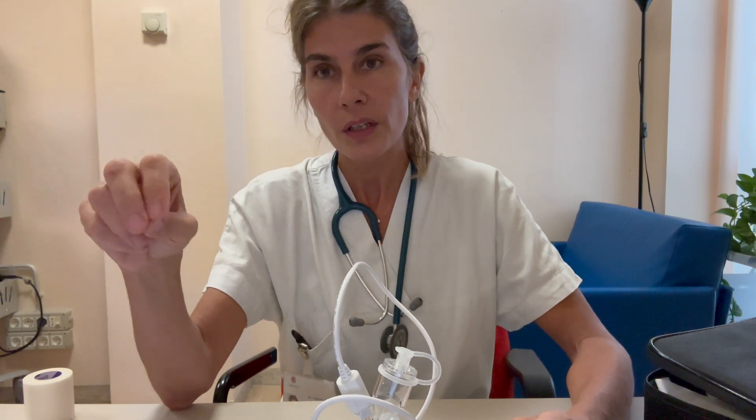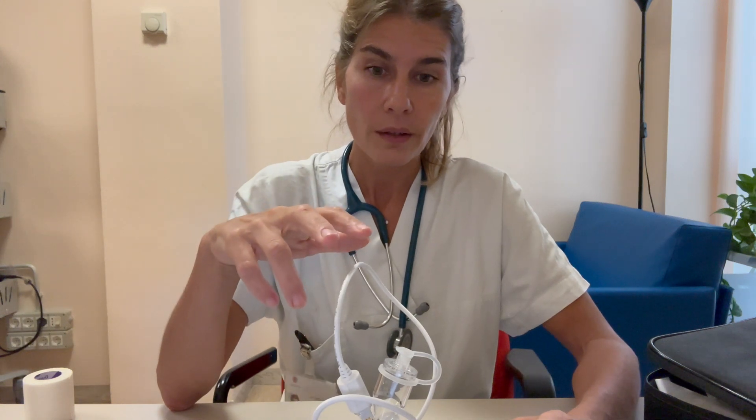Additional and continuous flows coming from jet nebulizers can alter NIV monitoring and tidal volumes, and it's not recommended to use jet nebulizers under NIV. So in that case, the patient needs to stop the therapy, stop NIV and start doing the aerosol, and only when they finish the aerosol can NIV be reconnected.